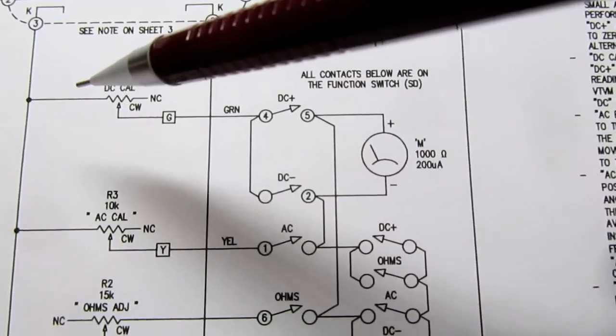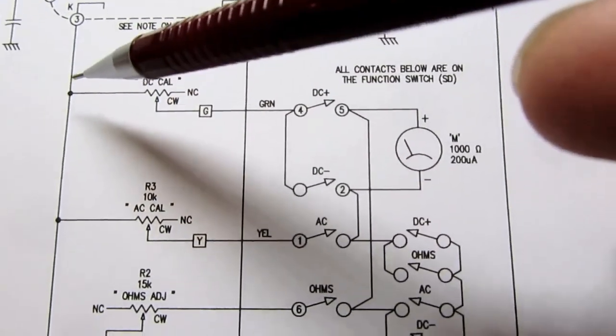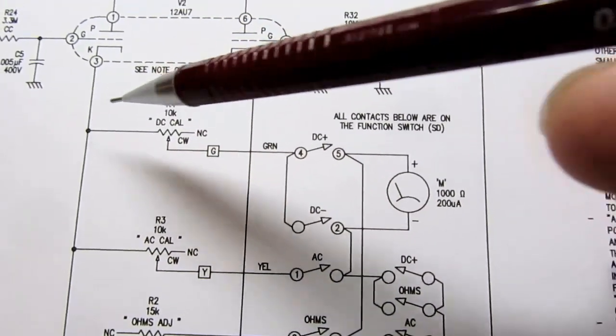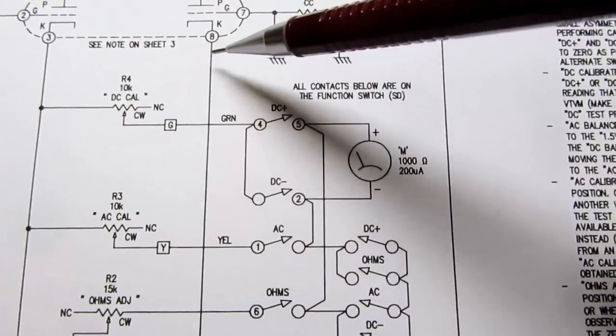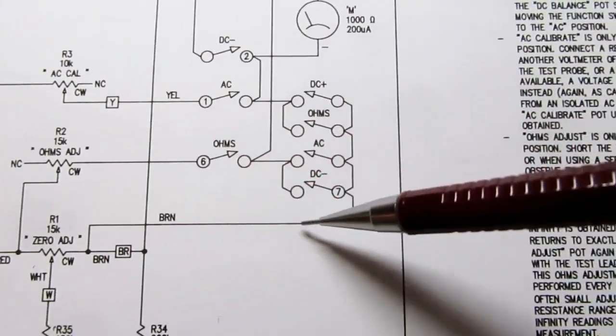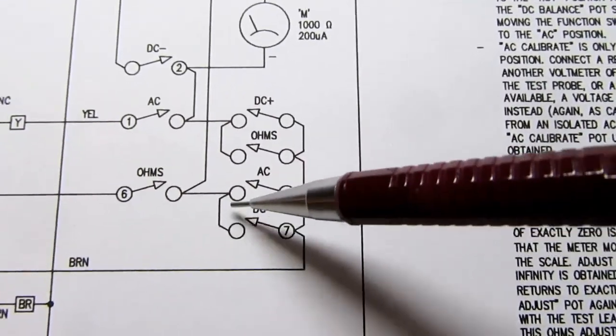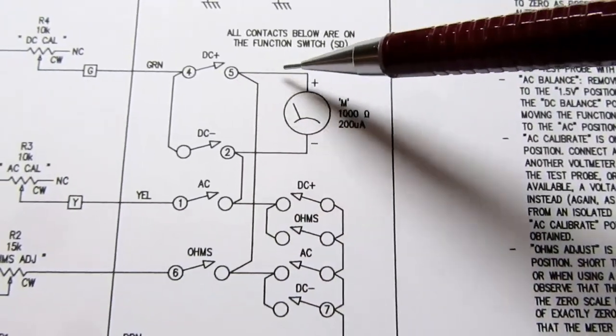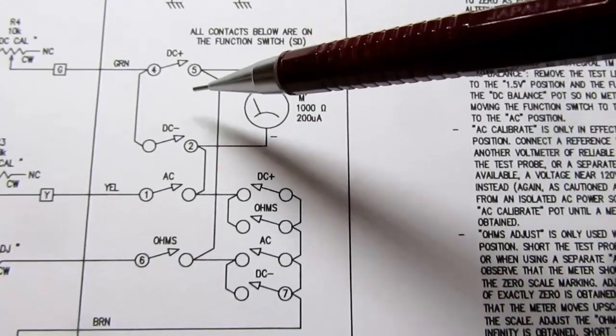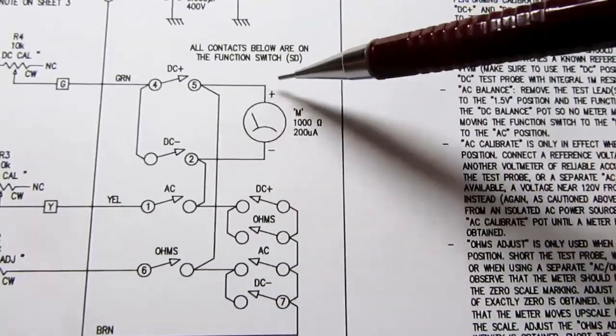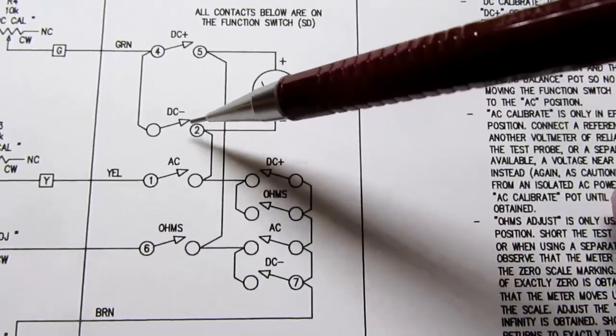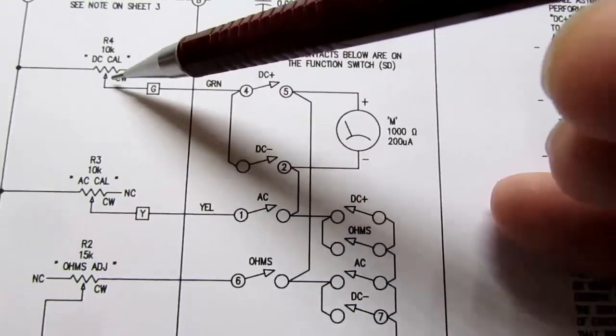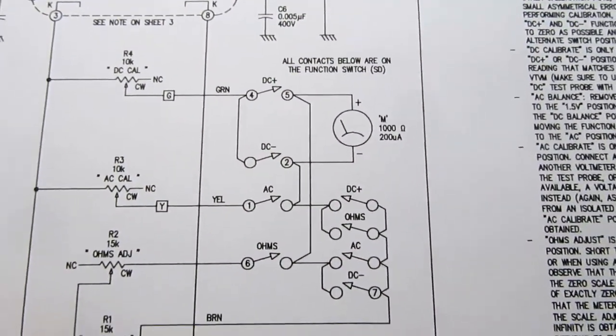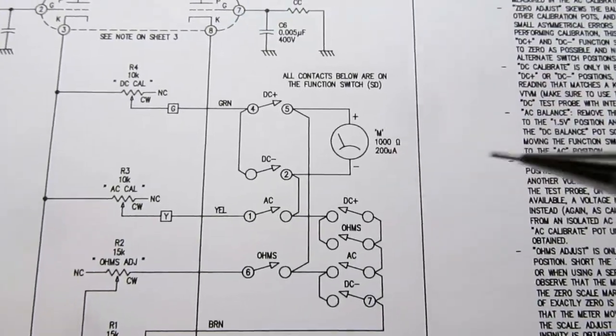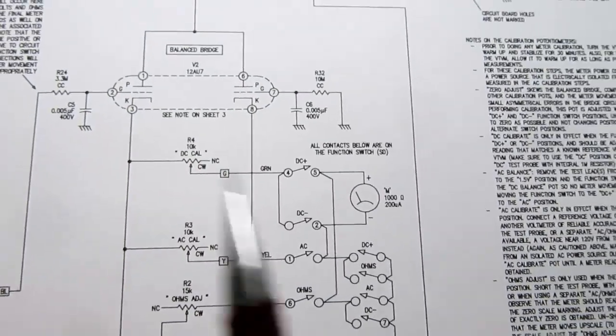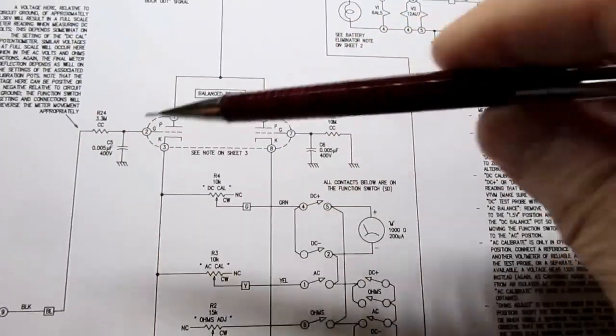So let's follow this through. This side, well, we know that this side is a higher voltage than this side now, so let's presume current is flowing in this direction. So let's start out by going down here, we come back around, we go up here, we go through the DC minus contact, and now into the plus side of the meter. We want current to go from the plus to the minus, so the current's flowing in this direction. It flows out the minus side, and now through this DC minus contact, back through the resistor to this side. So that's how the function switch has reversed the polarity of this meter movement across the bridge. So now you'll get a positive or an upscale reading even when you have a negative voltage being measured.